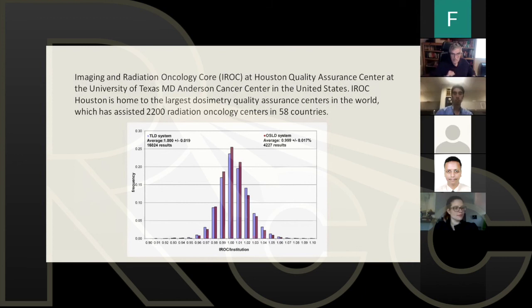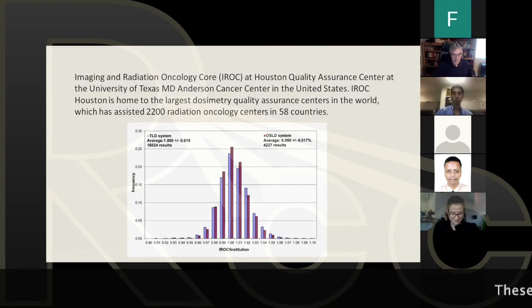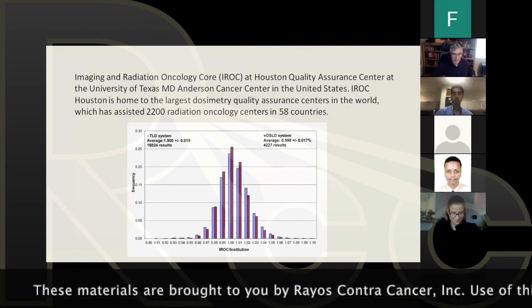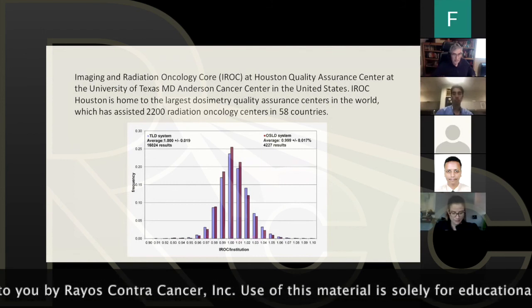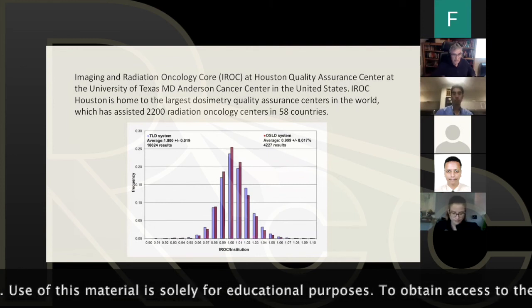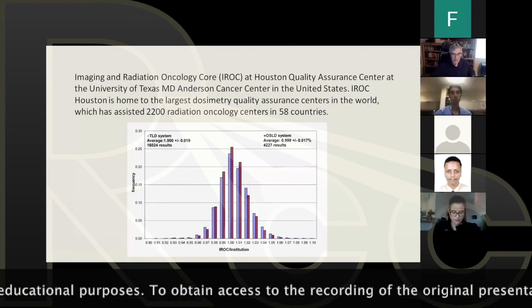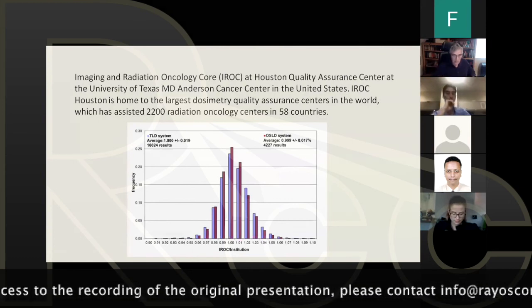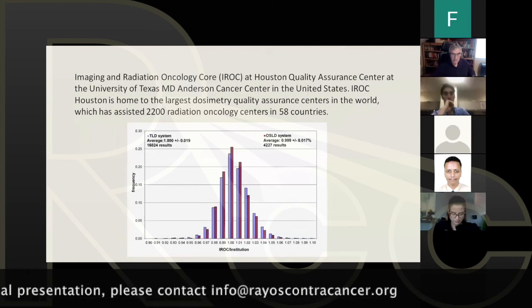And that happened to me once, a long, long time ago, many, many years ago, when I had to commission one of the first electron linear accelerators. I go back over 48 years. So I had to commission one of the first electron accelerators, and I did not calibrate it correctly. Luckily, we didn't treat any patients until I got the report back from the RPC, but they reported a 7% error, which I thought was correct. I said, no, this is how I calibrate it. They sent a physicist out with equipment to help me calibrate the machine. So that's how seriously they take it.